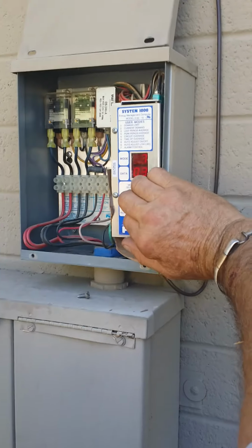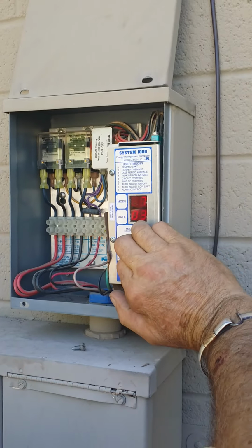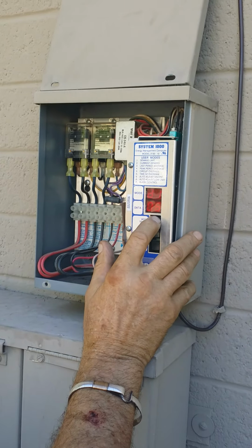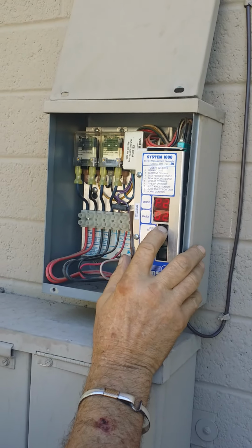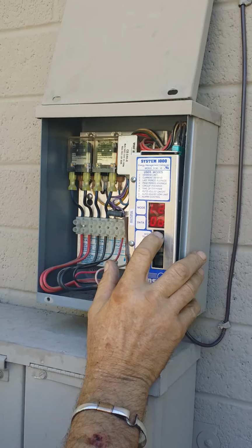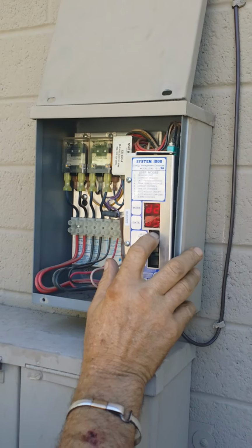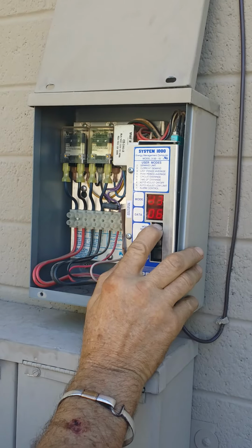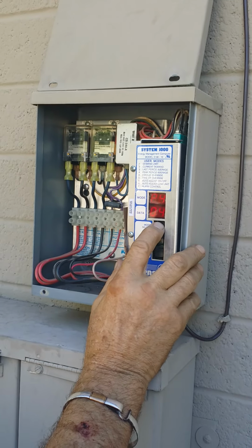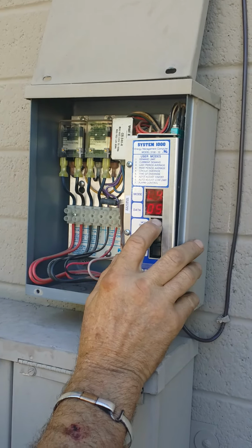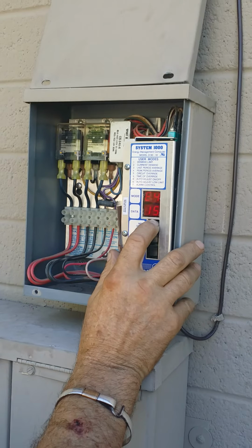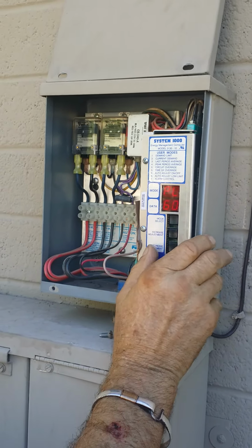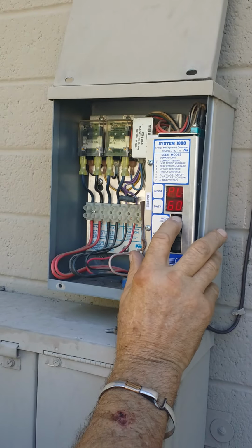You don't need to get into this, but this is the setup mode. I'm going to go through this again. P1 is a dryer, load of 6, enable 15, off for 6. P2 is the air conditioner. It's got a load of 8,000 watts, enable 15, off for 5. P3 is nothing, it's set at 15. P4 is a water heater, has a priority of 4, has a load of 5,000 watts, enable for 15, off for 6. And then PL, period length, is 60 minutes, which matches the meter.